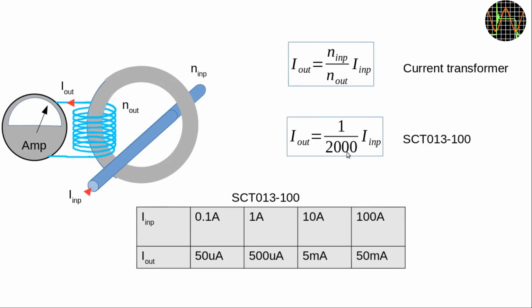In our case of the SCT013-100, these values are 1 and 2000, so the transformer effectively divides the current by 2000. What that means is shown in the little table here. The top row shows some example input currents and the bottom row the output currents the transformer will produce. A ratio of 1 to 2000 means you need to do some mental doubling, so measuring 5 milliamps on the transformer output, for example, means 10 amp is flowing.